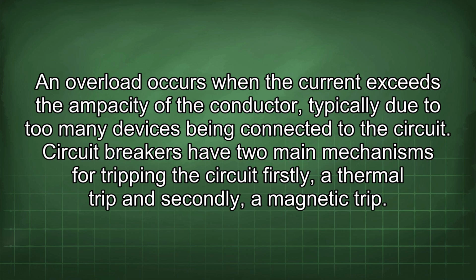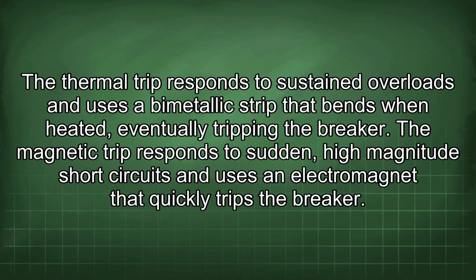Circuit breakers have two main mechanisms for tripping the circuit: firstly, a thermal trip, and secondly, a magnetic trip. The thermal trip responds to sustained overloads and uses a bimetallic strip that bends when heated, eventually tripping the breaker. The magnetic trip responds to sudden, high-magnitude short circuits and uses an electromagnet that quickly trips the breaker.